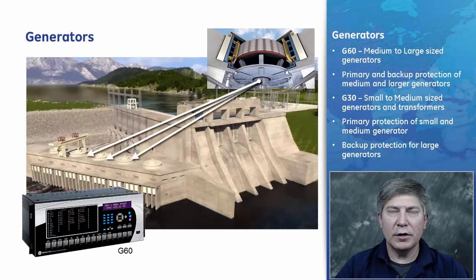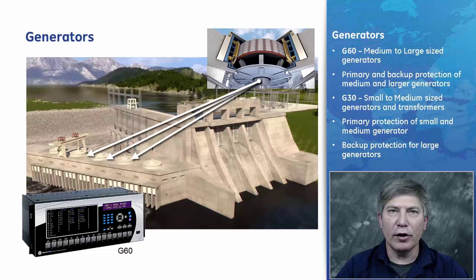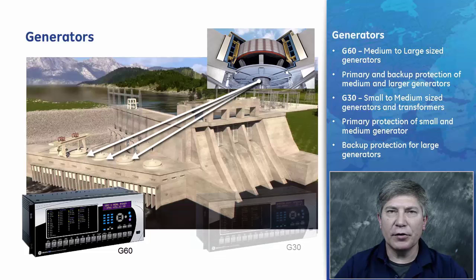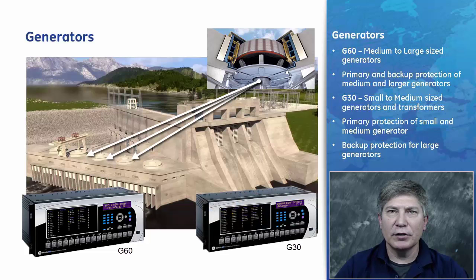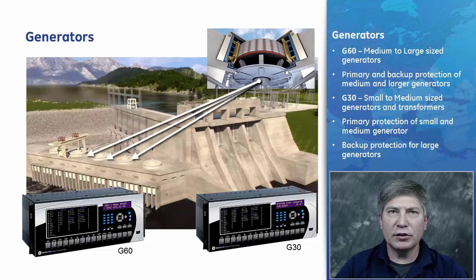Under generators, we have the G60 and G30. The G60 is used on medium and large generators, providing comprehensive primary and backup protection including large steam and combustion turbines, combined cycle generators, and multi-circuit hydro units. It includes advanced automation and communication capabilities, extensive I/O options, and powerful fault recording features. The G30 combines generator and transformer protection and is a flexible system for small and medium generators, generator and step-up transformer arrangements, or backup protection of large generators, also offering comprehensive protection and monitoring elements.